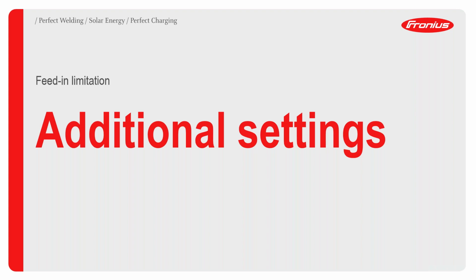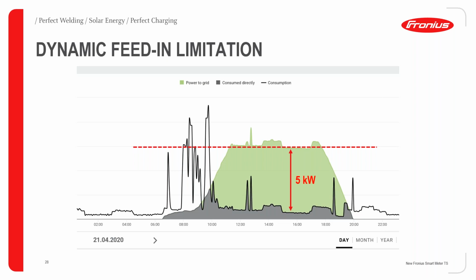Then additional settings. Apart from configuring the smart meter in the display and in the interface page of the inverter, what are the additional settings I can do with the smart meters? For example, you can do dynamic feed-in limitation. Maybe there is a restriction due to the fuse, or for example, a country like Germany, where the national regulation says that you cannot export more than 70% of your total system size. If you have a 10 kilowatt system, then you cannot export more than 7 kilowatts. So in this situation, you have to limit your system to 7 kilowatt or 5 kilowatt, whatever the situation.